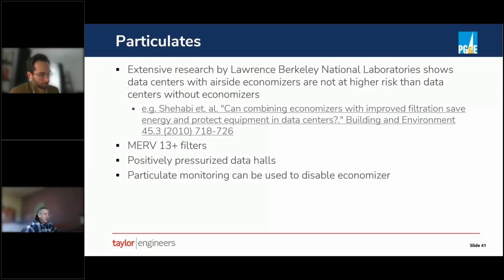Now, we have worked in data centers that have had issues with particulates and basically dust, even though they had MERV 13, and that was because the data center wasn't kept at a positive pressure. And so not all the air getting into the space was actually going through the filters. There was air coming through exhaust air openings that didn't have any filters and settling on the equipment and causing failure. So it's important to keep the space positively pressurized. That data center also ended up installing particulate monitoring. So they were measuring not only the particulate levels in the space, but also in the outdoor air. And if it was a particularly poor air quality day, they actually would shut off their economizer to try to minimize their risk.